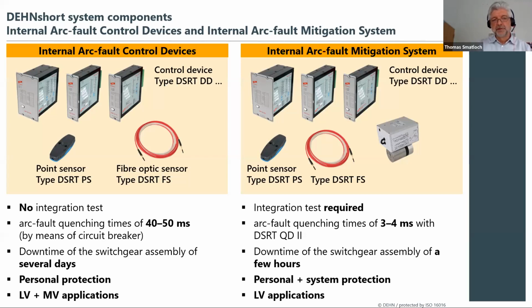So for the left-hand side, there is no integration test needed, and we have an arc fault quenching time of 40 to 50 milliseconds, depending on the breaker, because the signal from this controller is connected to the regular breaker, which is within the installation. And when the controller gets the information, okay, there is a strong light in connection with a big current flowing, that means this is an arc fault, and then the breaker is triggered to switch this off.